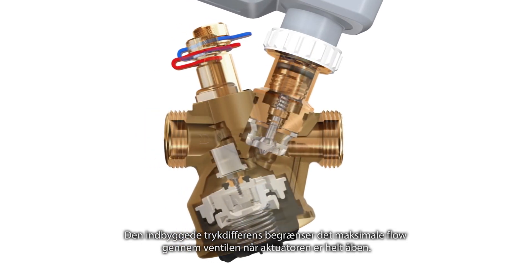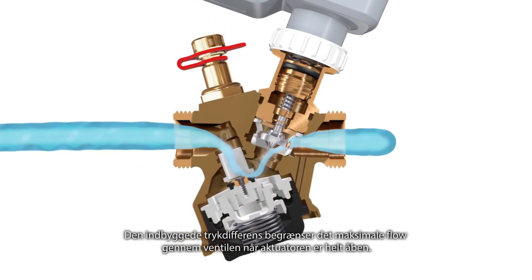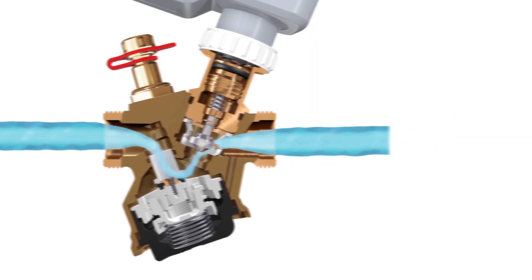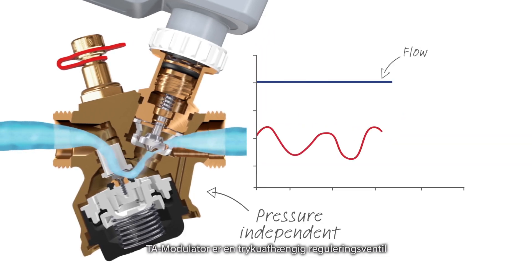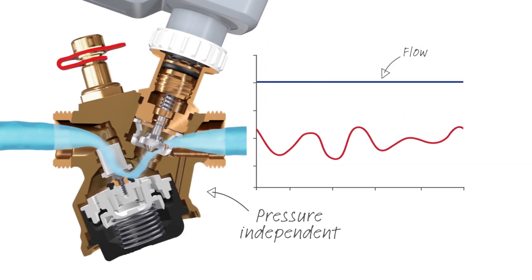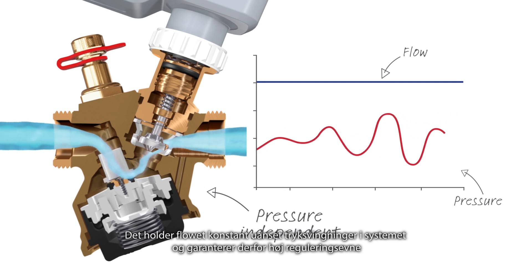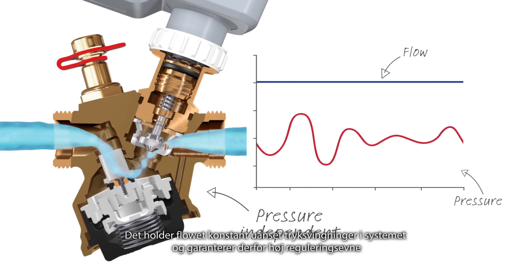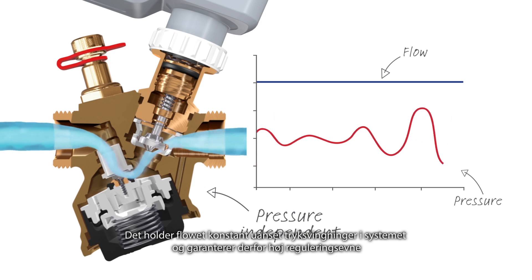The built-in pressure controller limits the maximal flow through the valve when the actuator is fully open. TA modulator is a pressure independent valve. It keeps the flow constant regardless of pressure fluctuations in the system and guarantees high control authority.